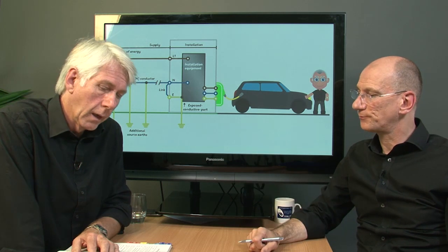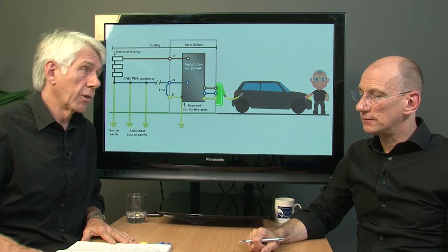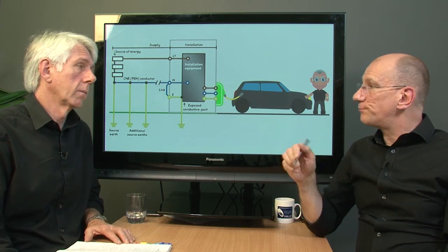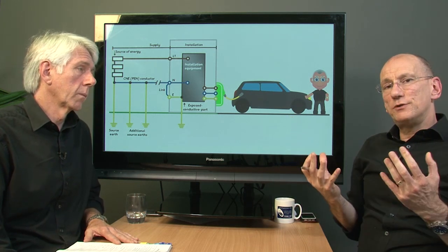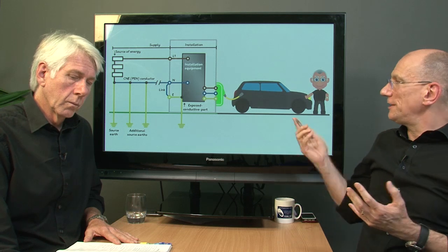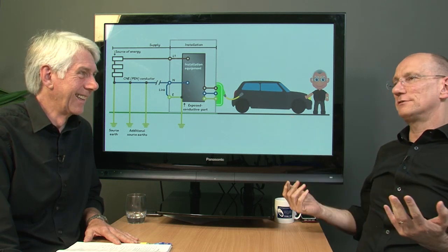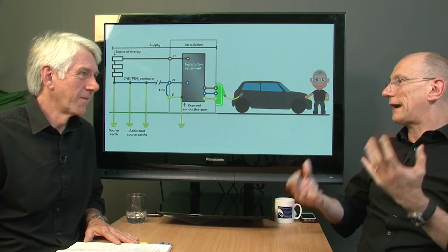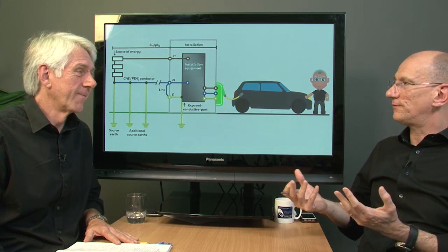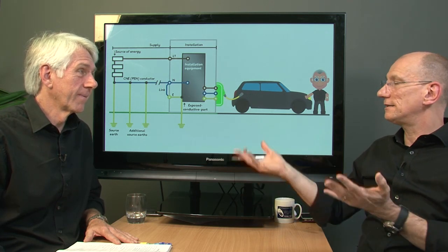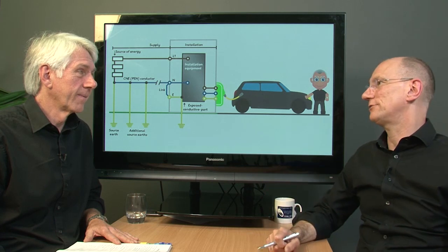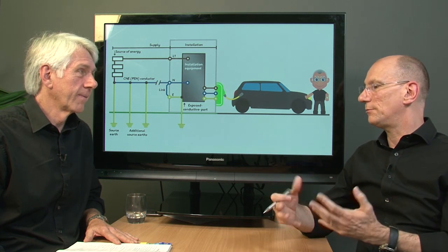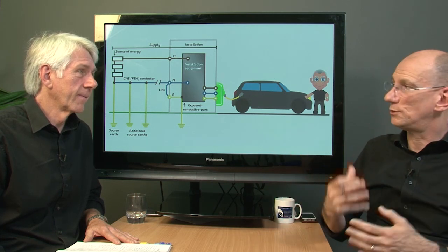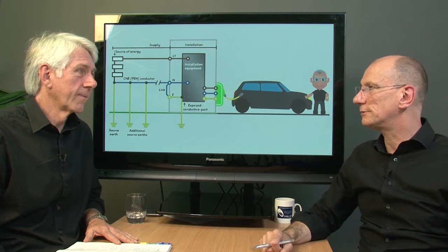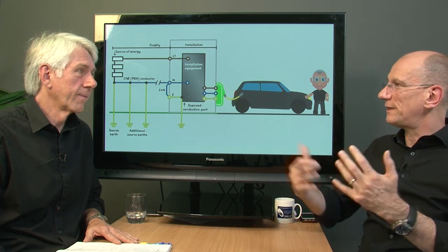Its operation time is less than 4 seconds for a 50 volt rise - well, between 4 and 5 really, because with the 4 seconds, you wouldn't want to get home at night after a long day, plug in your charger, and there's a little power outage at 2 in the morning for 3 seconds and the thing didn't re-engage, and you come out with a flat battery. So it's given a little bit of time, but if you've done your courses and training, we don't really want any metalwork to be live for more than 5 seconds. So there's a bit of a compromise there.